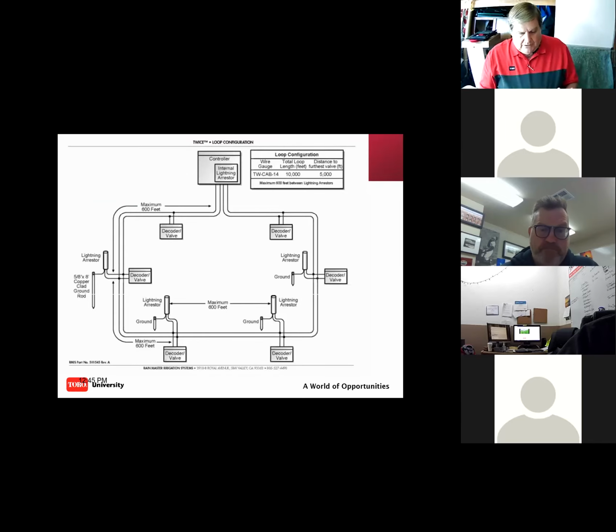Granted, you may not have been the installer, in which case you don't know if it's a loop wire path or not. In which case, what do you have? I remove the 2-wire paths and leave only one connected. Check it. Is my current draw normal now? Check the other 2-wire path. Is that one normal? And check each one of them and find the one that's got the high current draw and then follow it out into the field.